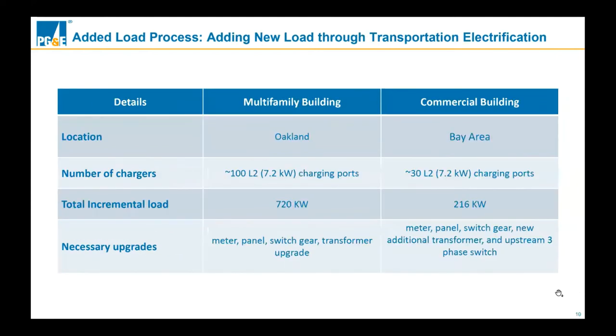All right, next slide. This one is looking at transportation electrification, and this one isn't illustrative—it's based on a couple of real examples in the Bay Area. We have a multifamily building somewhere in Oakland that installed around 100 or so Level 2 charging ports, for a total incremental load of around 720 kW. The necessary upgrades as a result of that incremental load were a meter panel, switchgear, and a transformer upgrade.